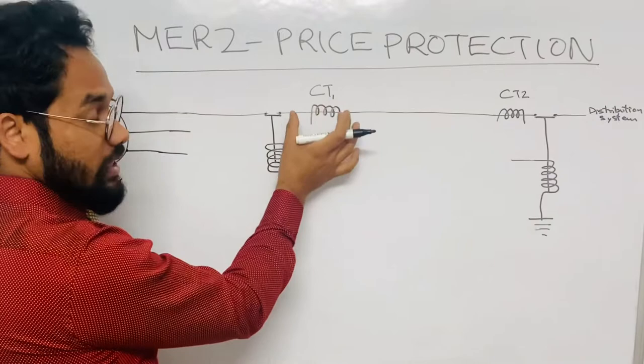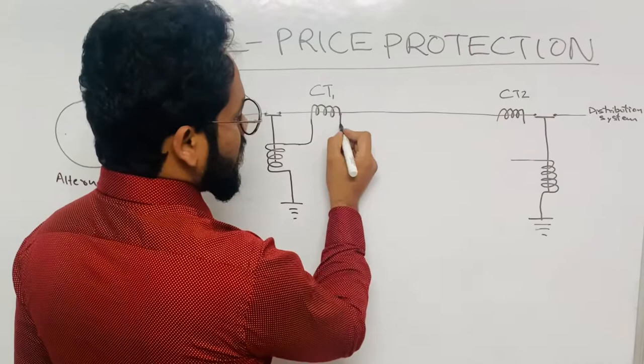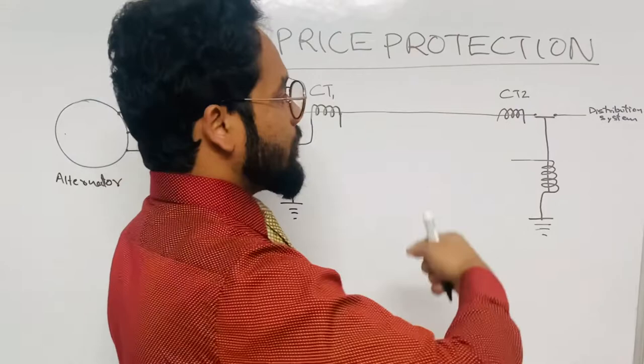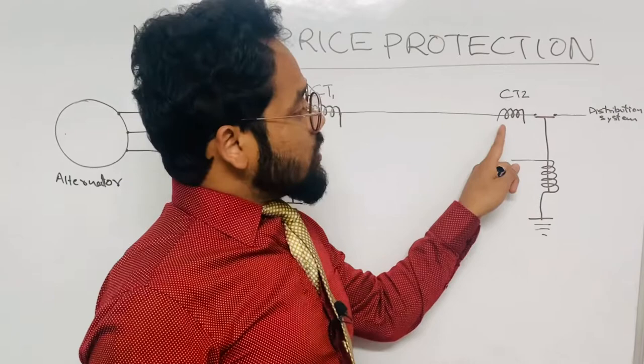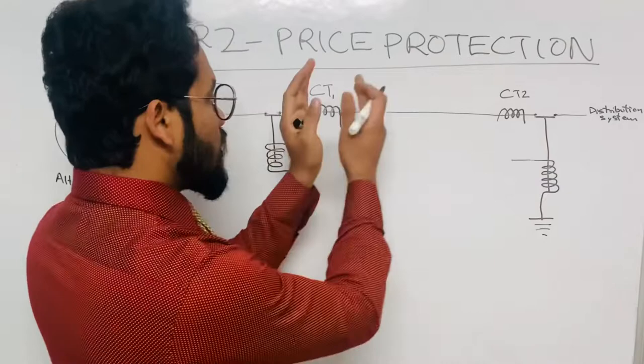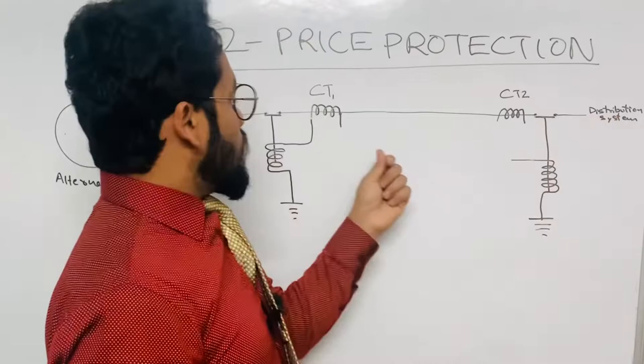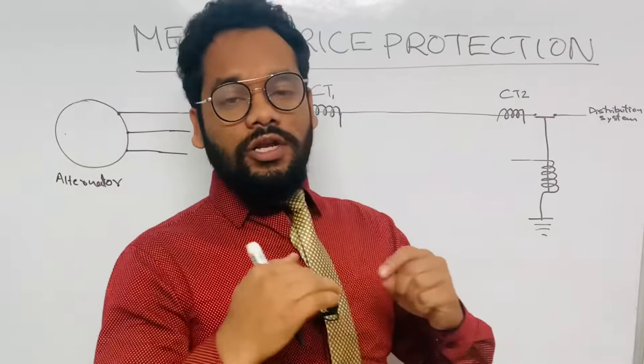CT1, placed near the source, monitors the current output from the alternator and is connected to the relay coil on that side. CT2, placed near the distribution system end of the feeder line, monitors the input current to the distribution system. So one current transformer is at one end of the feeder line and the other is at the other end towards the distribution system.